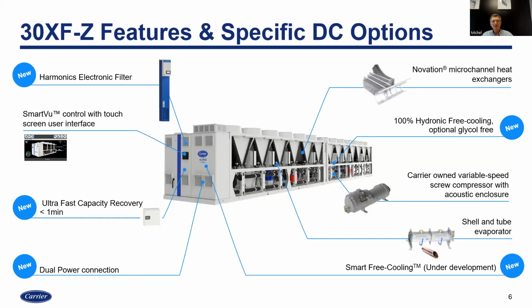We can also benefit from minimum energy consumption due to the reduction of the flow. You don't need to maintain relatively high flow, and it also reduces the benefits of free cooling. I will probably talk later about this. So this is, in one slide, some of the options. I'm not talking here about integrated hydronic options. Of course, we have hydronic pumps of different sizes. We can manage as much as 300 kilopascal available static pressure. So it can be a primary or secondary pump, already included in the chillers. Okay.